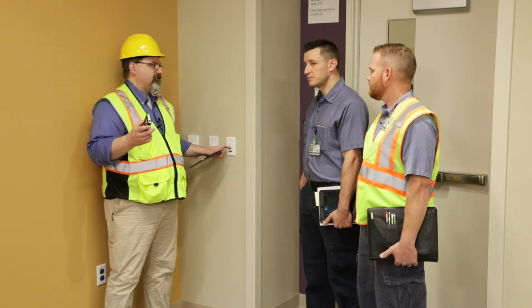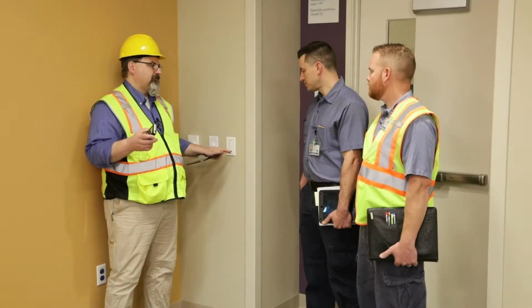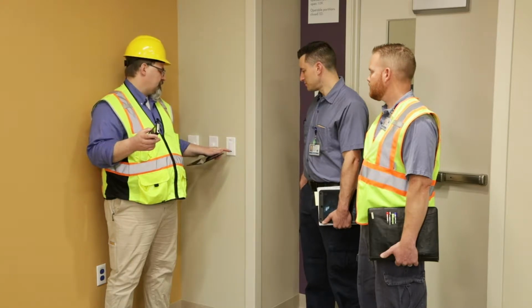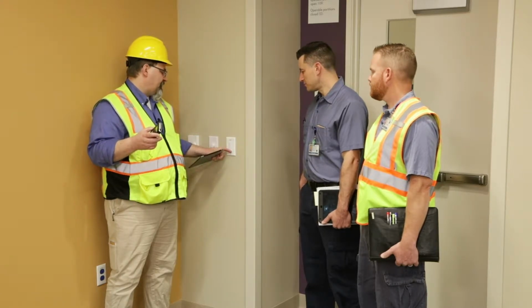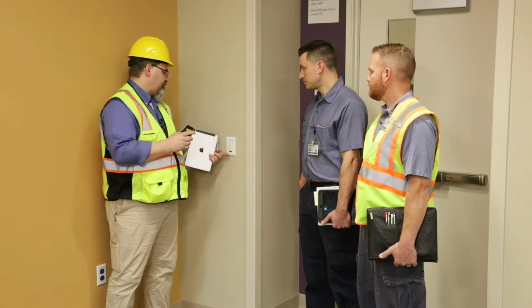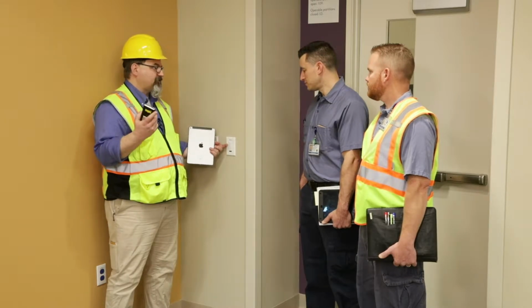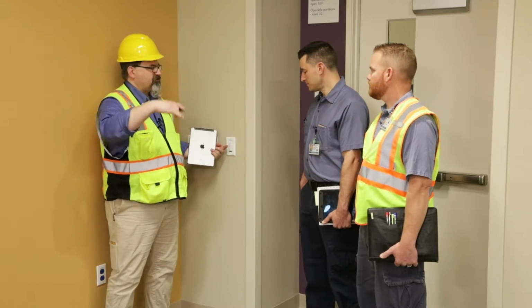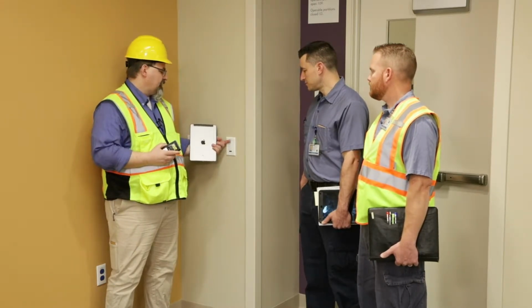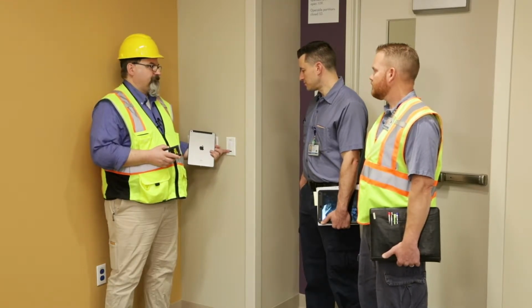Like in certain rooms, it'll be a load. So this will actually turn the light on and off, right? This one's a load, so somebody's been here already. If it comes out of the box, our devices have certain programming called plug and go, right? If this comes out of the box and you replace it, it's going to see what's in the room by its serial number. It's going to associate itself with a certain hierarchy, and on this one button, it'll control every light in the room, right?